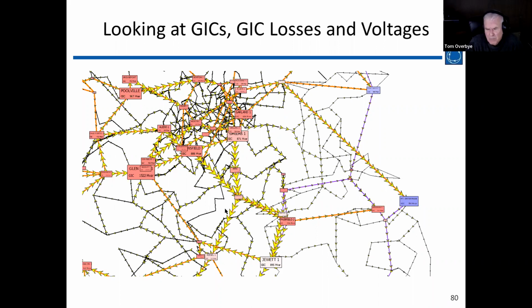Another important point, which I mentioned at the beginning, is that when you do these studies it's really important to make sure your generator step-up transformers are in the correct configuration. For most generators, if they're out of service, their GSU is out of service as well. So in the power flow they need to be modeled correctly, because that transformer becomes another path to ground. With HEMP, sometimes you want paths to ground because you want to shunt some of these GICs to ground.